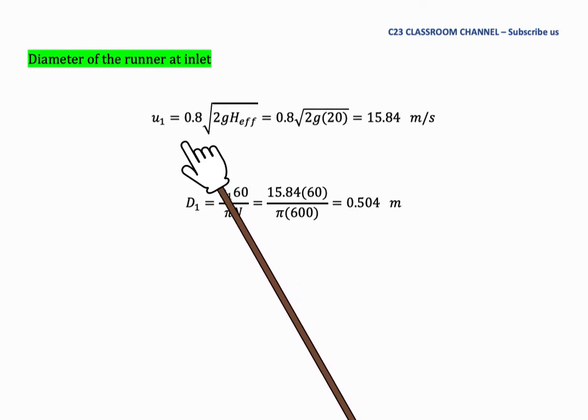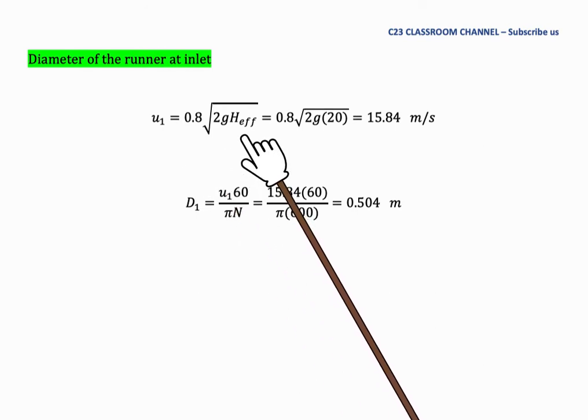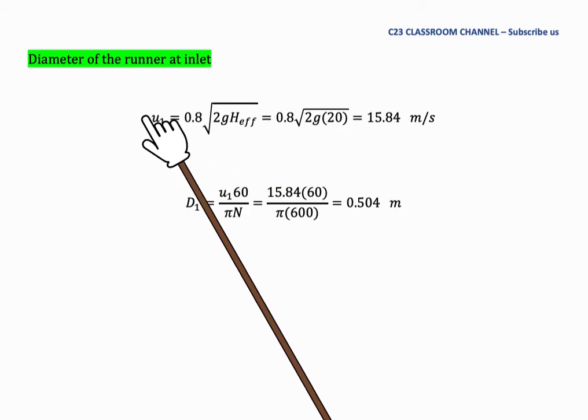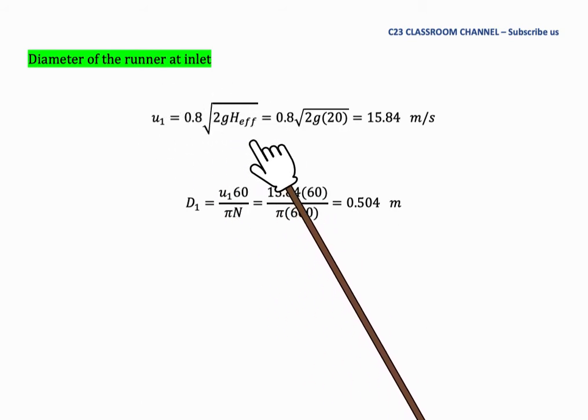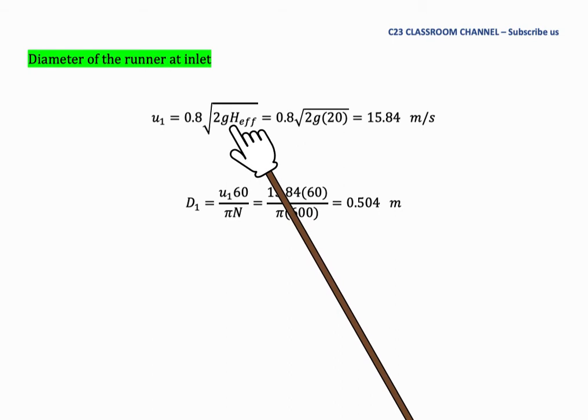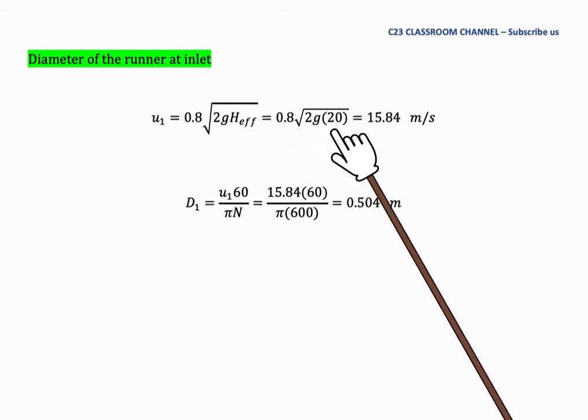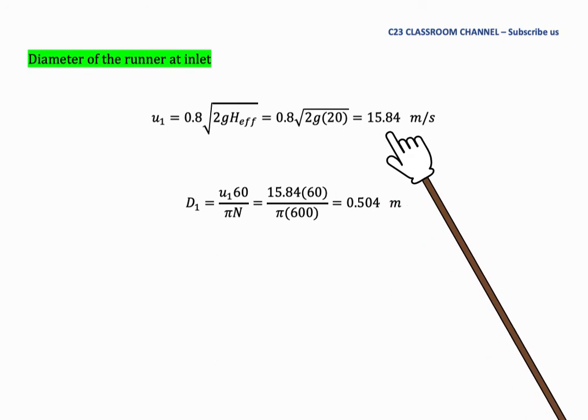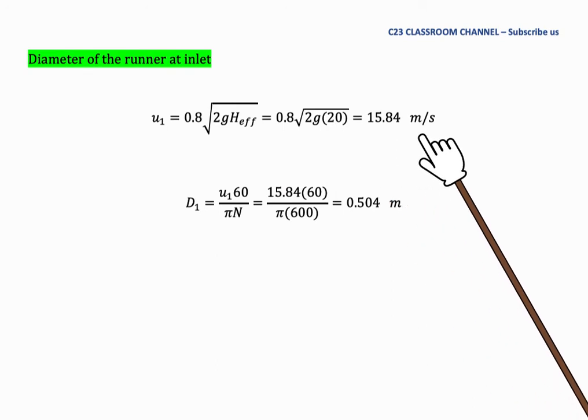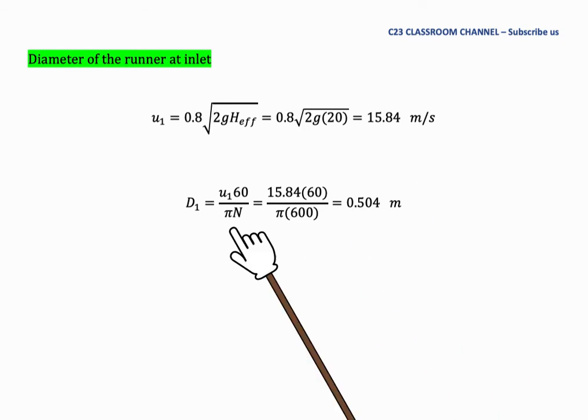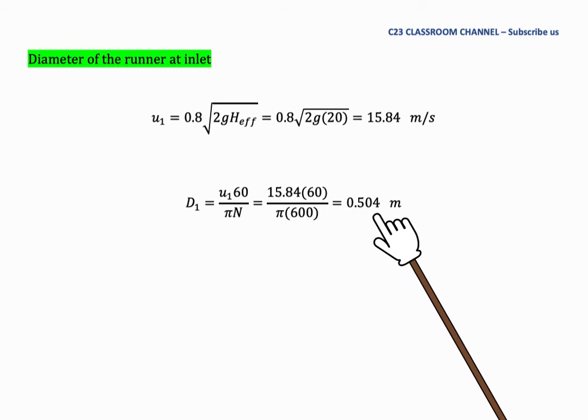U1 can be calculated using this equation given in the question. We substitute the value of H here with H effective which is equal to 20 meters. We get U1 is equal to 15.84 meters per second. We substitute in this equation and get D1 is equal to 0.504 meters.